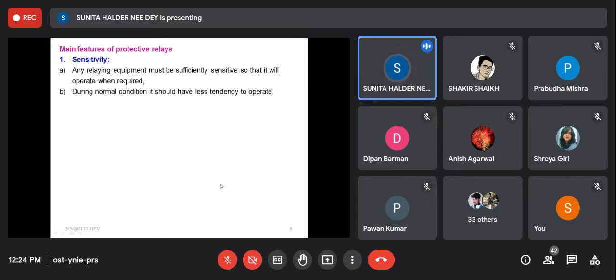But generally, a relay does not have this type of sensitivity, so we have to sacrifice it. We may set it for 600, 700 like that, but not for 500, 500.1. And that is also not required, because due to some overloading on the consumer side, which we do not know about, there is an uninformed overloading.